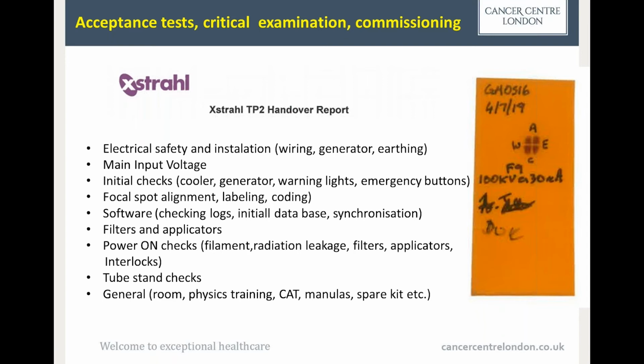And this identification of applicators is simple and straightforward, just to simplify setups. We also have all these manuals and documentation, and you can see on this slide that the center of the focal spot position was checked with a special collimator which was brought by the engineers. It is a pity that the client can't have it, but I can imagine that it is a very proper, specific tool to verify. Looking at the construction, it would be rather impossible for the center of the beam to shift, unless the head is hit somewhere.